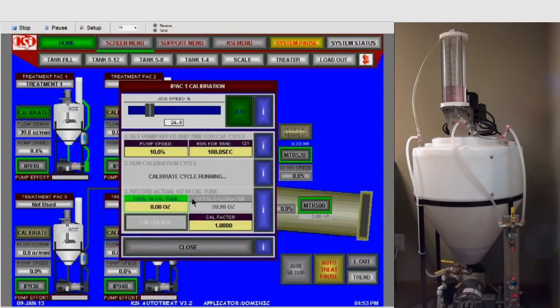So say our flow meter accumulates, totalizes to 70 ounces, and we look at the cal tube and we read 90. Well, something was probably not right because we're farther off than is typical. We either didn't start at 0 or we read the tube wrong. If this was at 75 and we put 90 in here and pushed calculate, since that is outside of our 15% over or 15% under window, it's going to abort that, and it's going to say rerun calibration cycle or re-enter a new value. At that point, we can decide if we had a wrong reading and enter the correct one, or if we return the liquid to 0 and run it again.